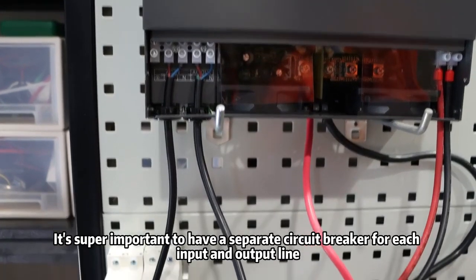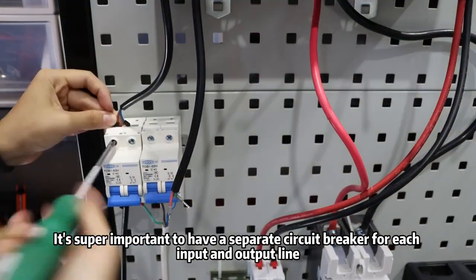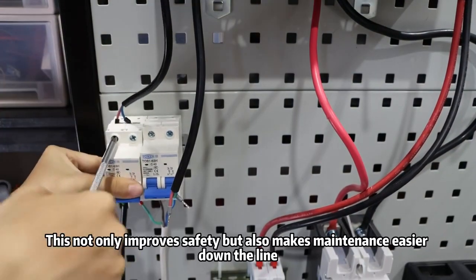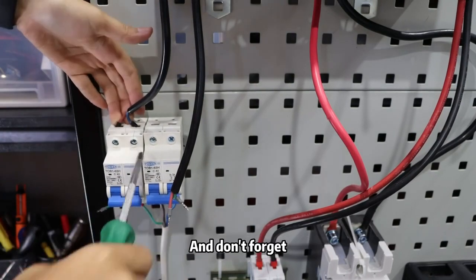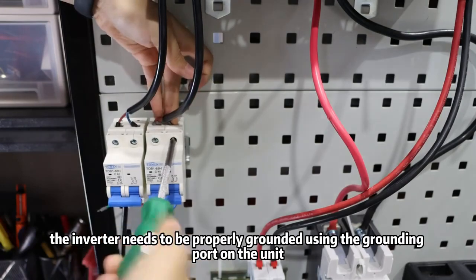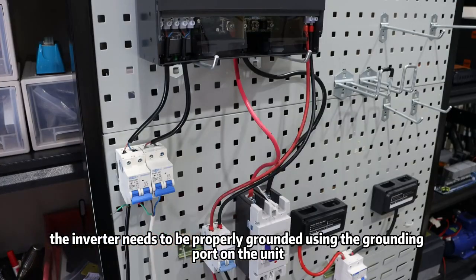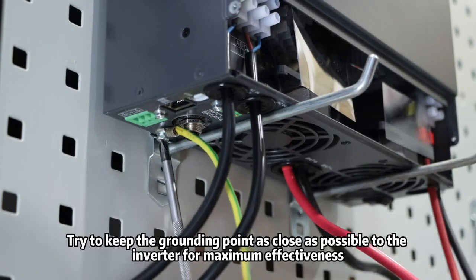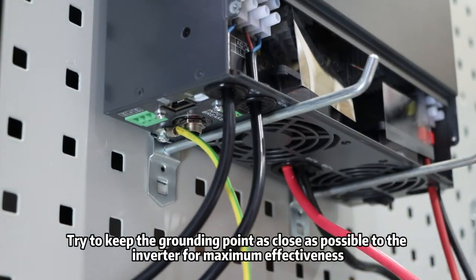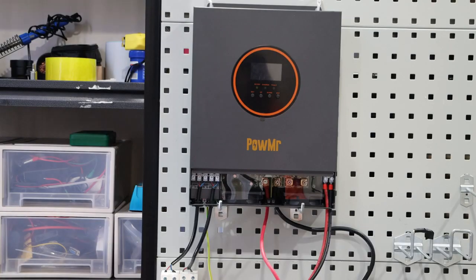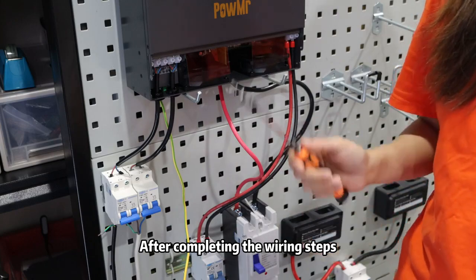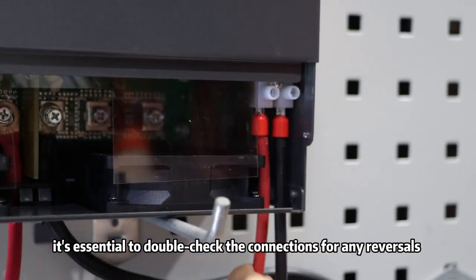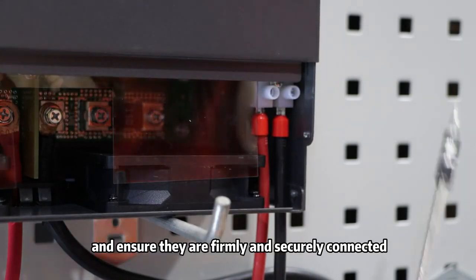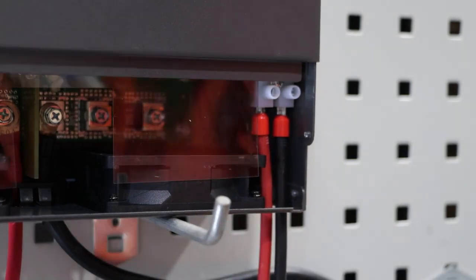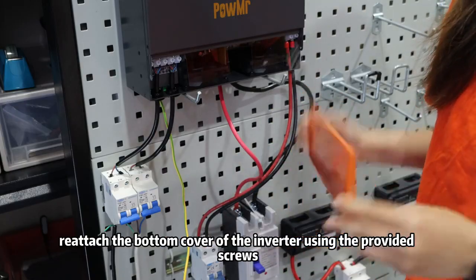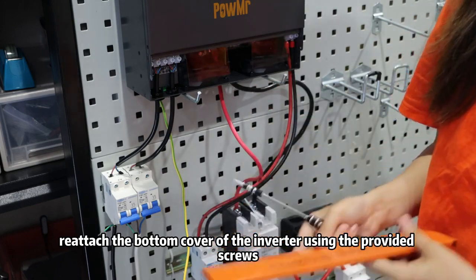It's super important to have a separate circuit breaker for each input and output line. This not only improves safety but also makes maintenance easier down the line. And don't forget, for your own safety, the inverter needs to be properly grounded using the grounding port on the unit. Try to keep the grounding points as close as possible to the inverter for maximum effectiveness. After completing the wiring steps, it's essential to double-check the connections for any reversals and ensure they are firmly connected. Once verified, reattach the bottom cover of the inverter using the provided screws.